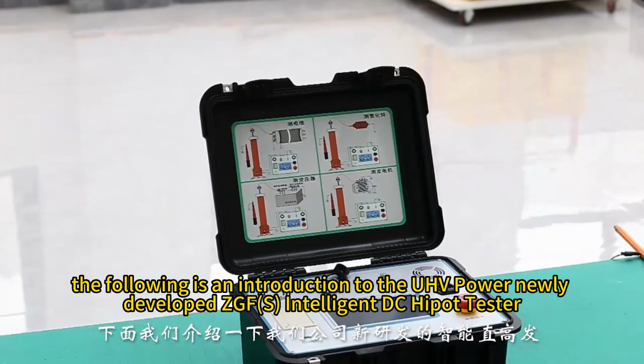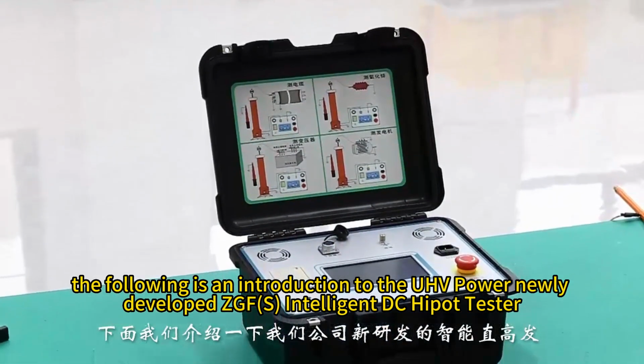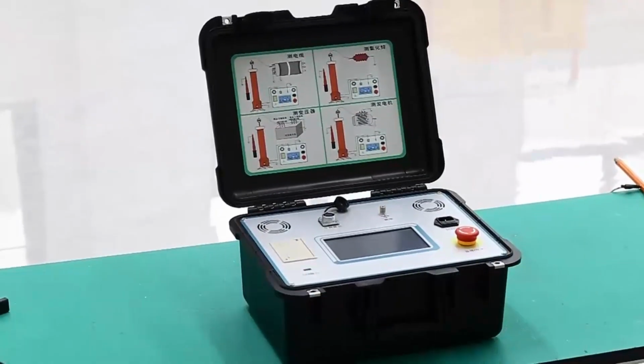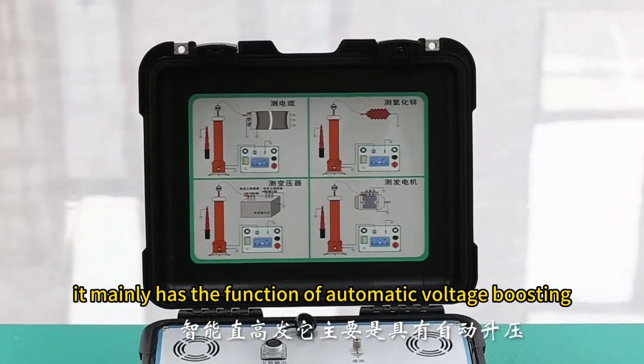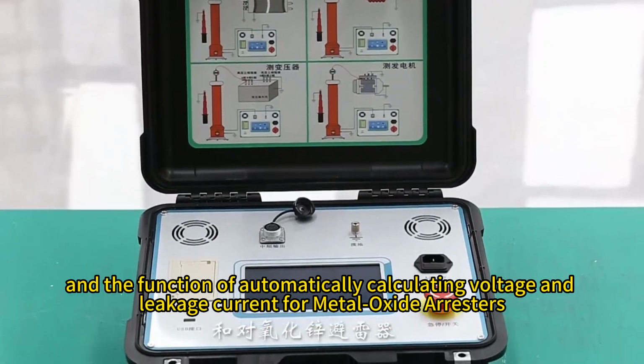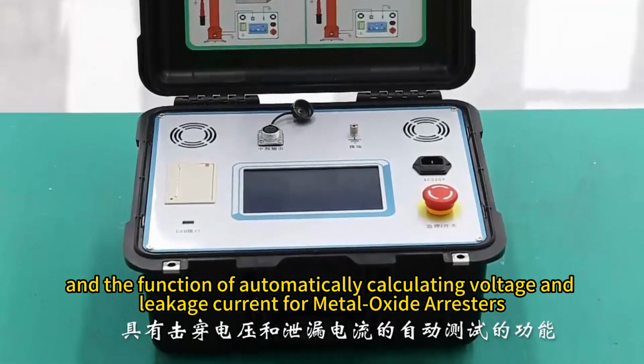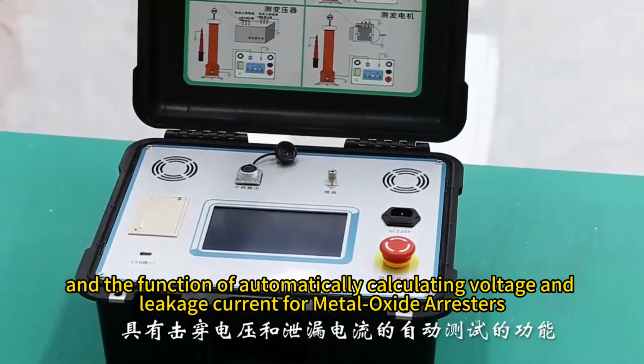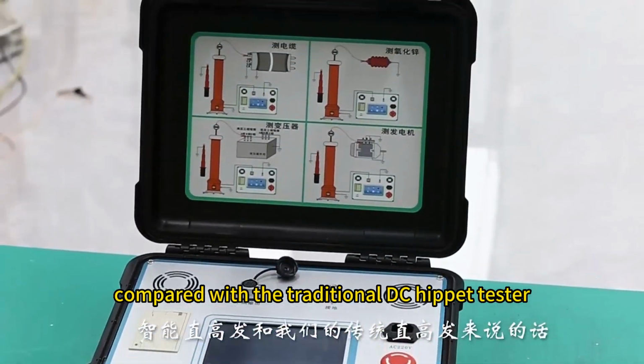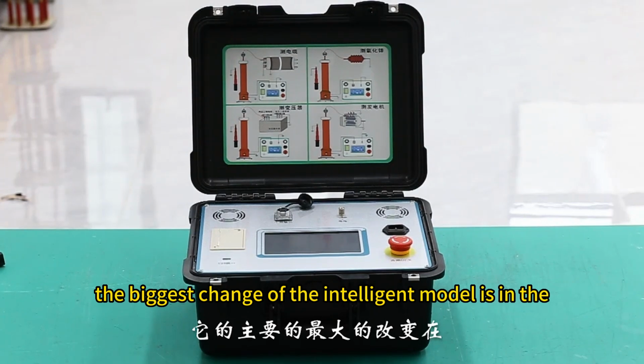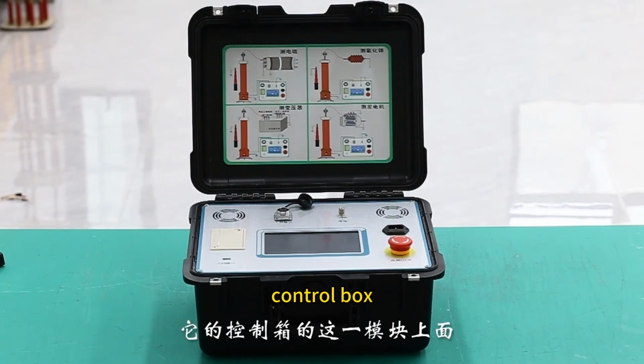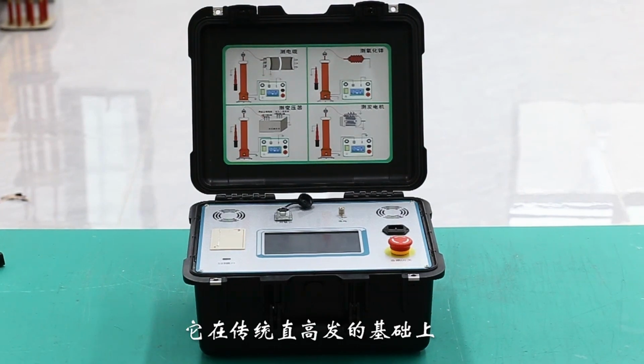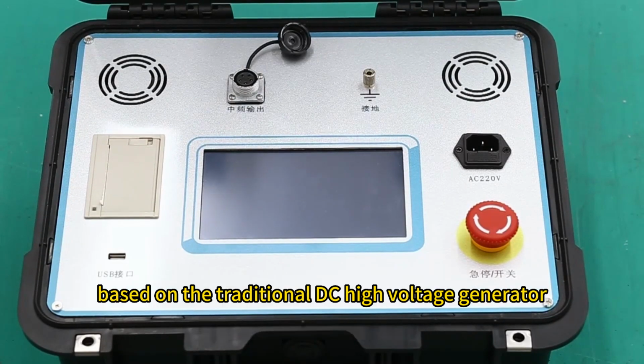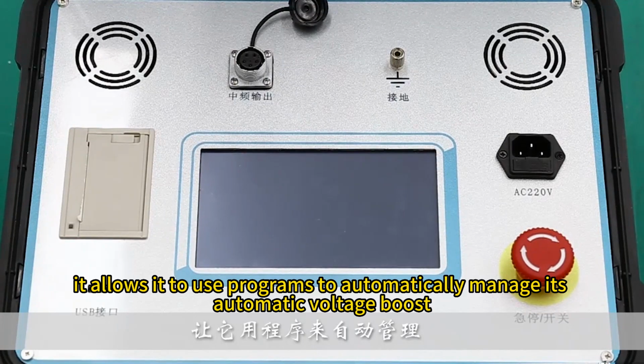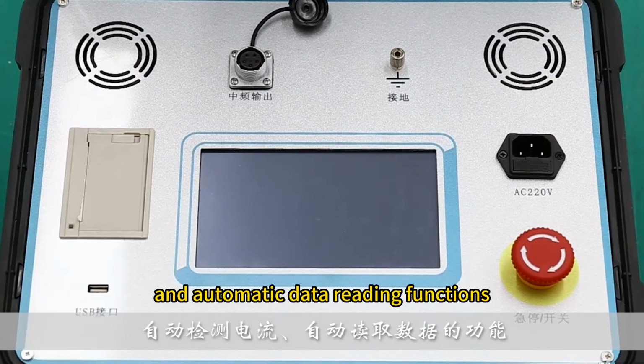The following is an introduction to the UHV Power newly developed ZGF(S) Intelligent DC Hipot Tester. It mainly has the function of automatic voltage boosting, and the function of automatically calculating voltage and leakage current for metal oxide arresters. Compared with the traditional DC Hipot tester, the biggest change of the intelligent model is in the control box. It changes the control box based on the traditional DC high-voltage generator.